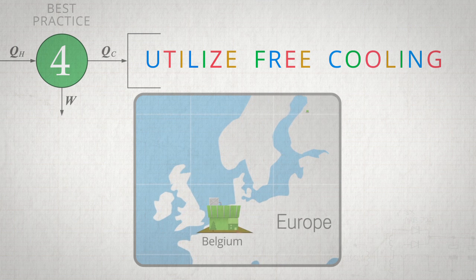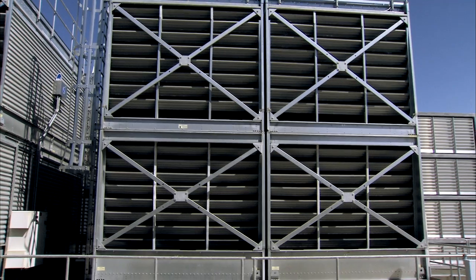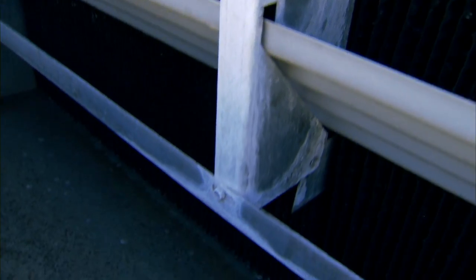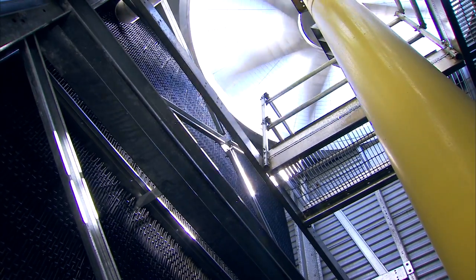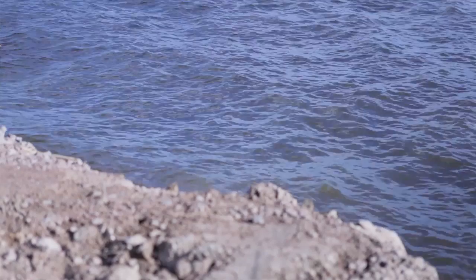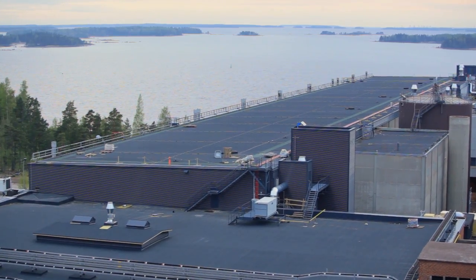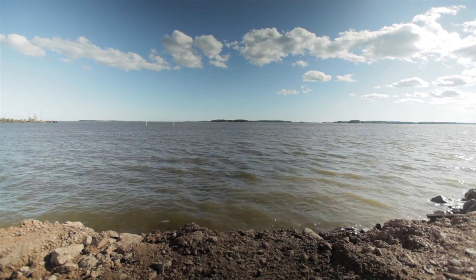In Europe, we have two data centers that have no chillers whatsoever. We're able to take advantage of local constraints and conditions. In Belgium, we use evaporative towers without any chillers given the ambient conditions. In Finland, we use seawater cooling. Seawater from the Bay of Finland cools the servers, and then we temper the water returning to the Bay of Finland so there are no temperature gradients returning to the Bay.